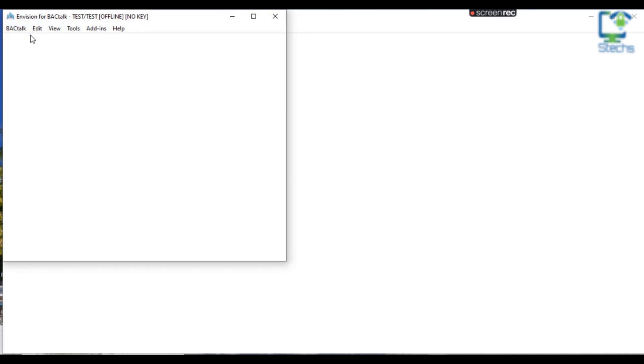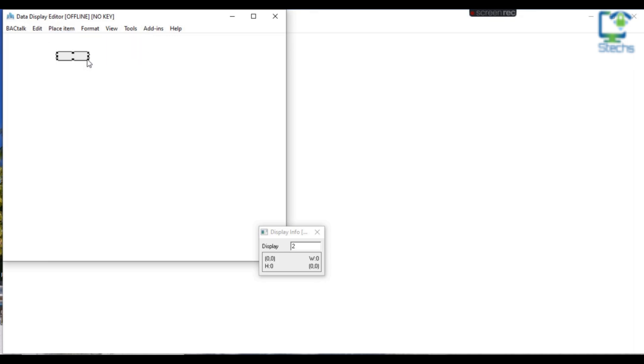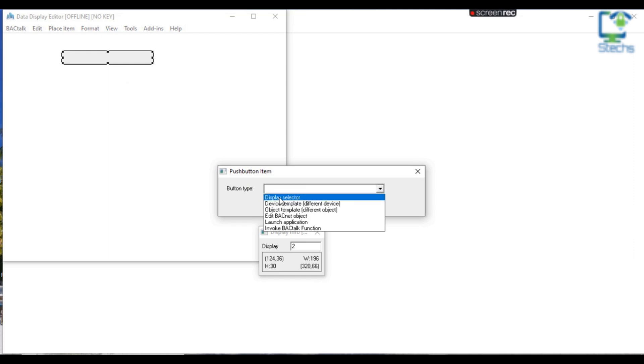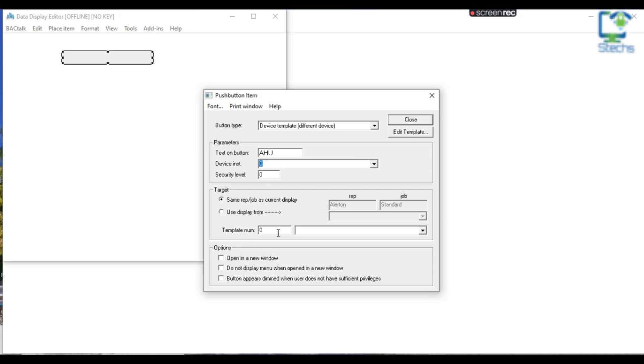When you click on the Systems Page button, a new window opens. Then click on Place Item from the menu bar and select Push Button Selector. Place the push button on the page, then double-click on the button to configure it. Select Device Template - Different Device from the options, because this push button will be configured for one device or one controller. Select the device instance in the Device Inst column. I am adding text for the button as "AHU" and selecting the device instance from the list saved in the Device Manager. Now I am selecting the template number for the particular push button, and in the options I choose Open in a New Window.